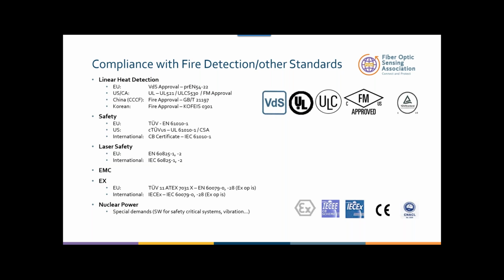What's also important is that we are compliant with the standard fire detection and other standards, certificates and certification requirements. We have VDS, UL, ULC, FM approval, TUV. Most importantly, when we start talking about tank farms, we also talk about explosion-proof areas. Explosion-proof areas are very, very critical, and with a system where you don't need to do a physical connection like a standard linear detection, you can just use a fiber optic sensing system and use a cable where you don't have to worry about whether the system is active or not, because at the end of the day we are only passive sensors. So that's very important.